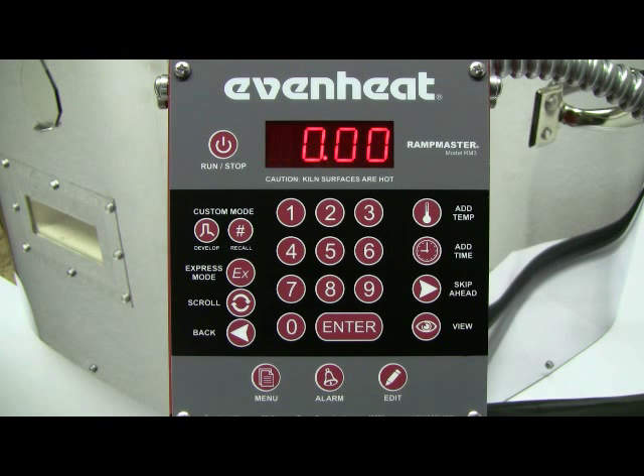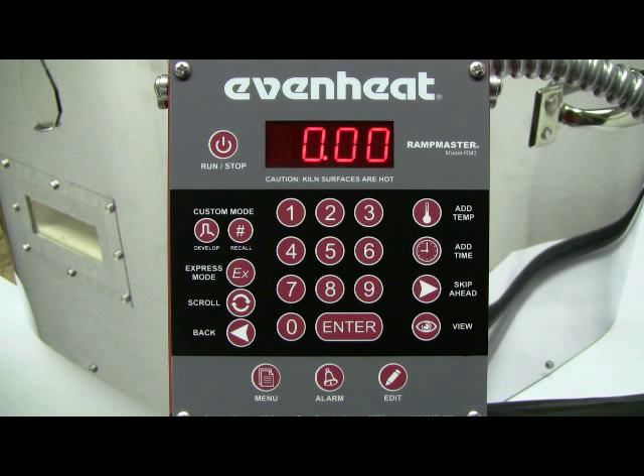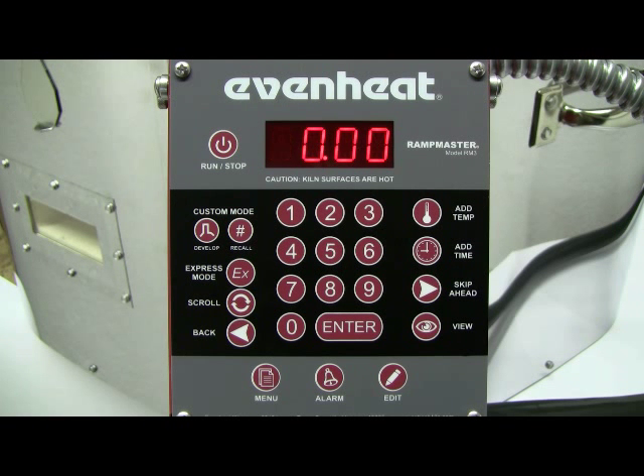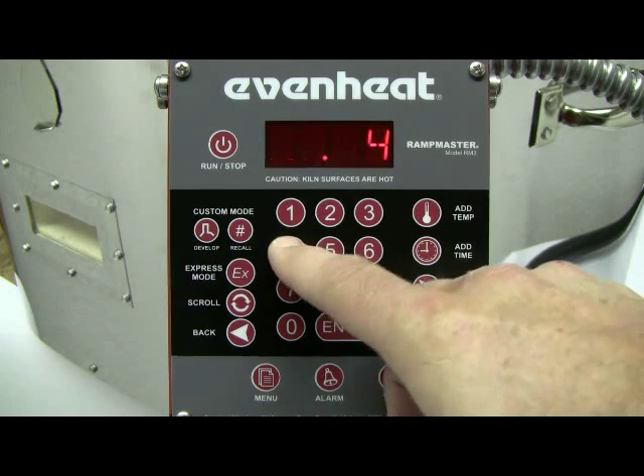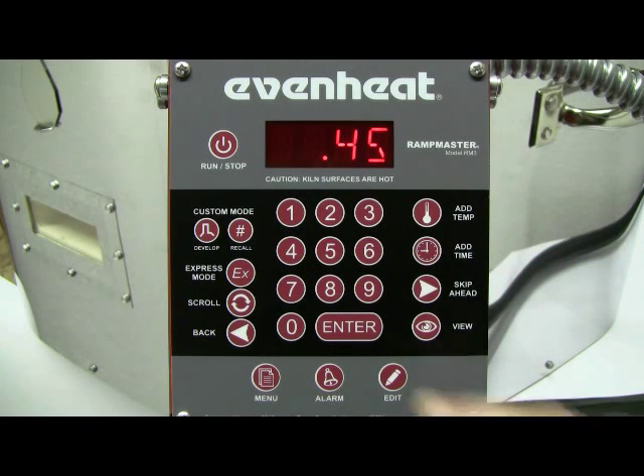The display now reads HLD3. The RampMaster is asking for the hold time at our 960 degree annealing temperature. We'll choose 45 minutes. Type in 45, then press the ENTER key to store your choice.